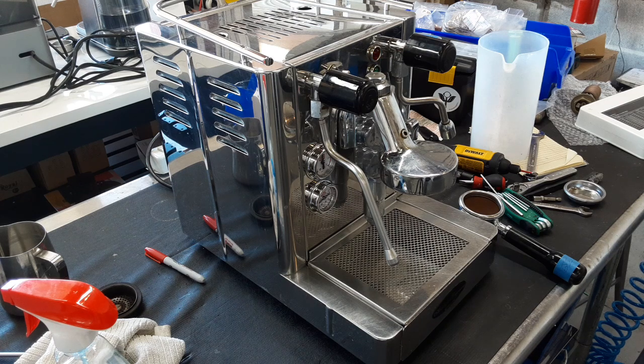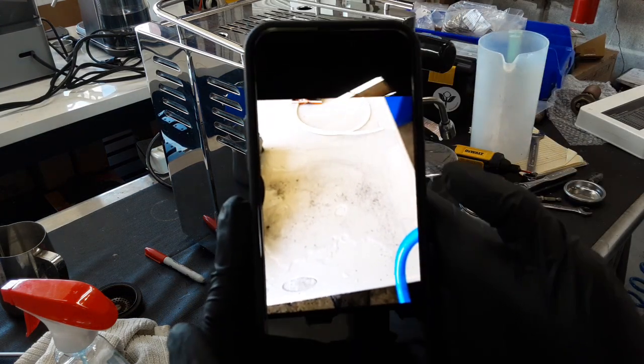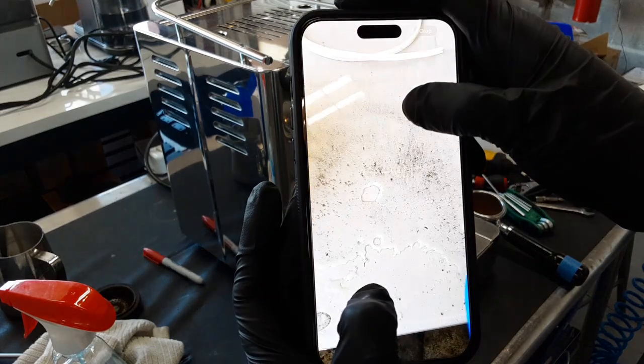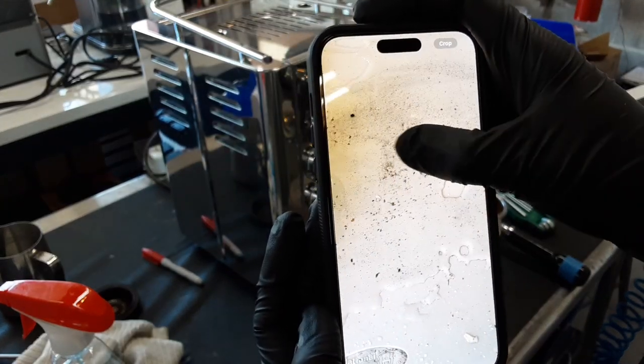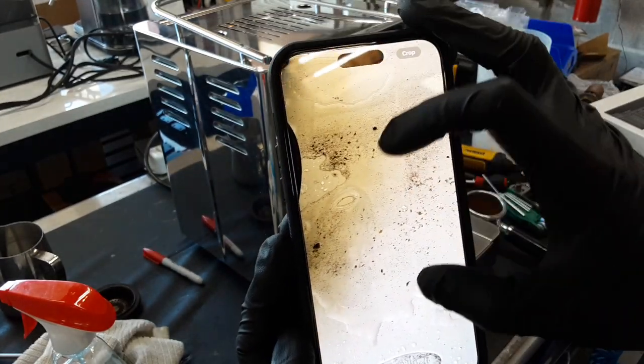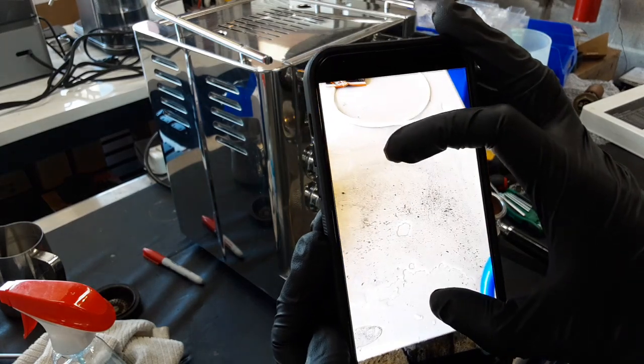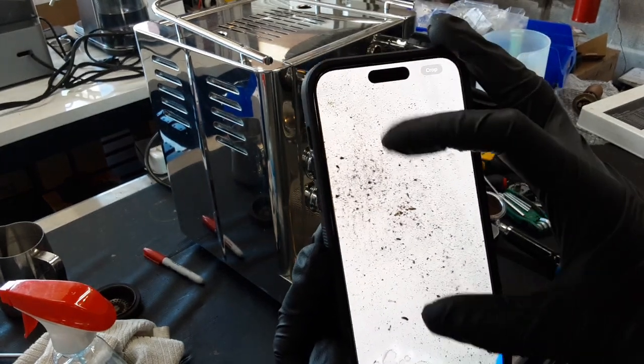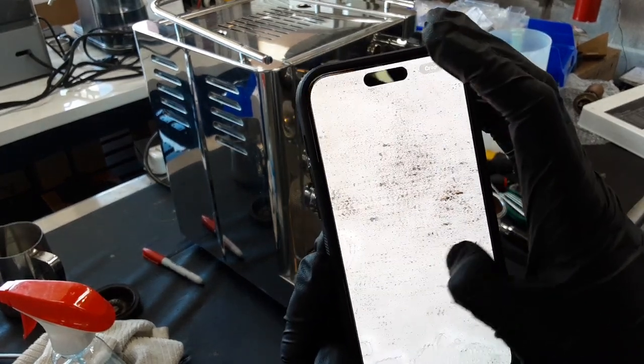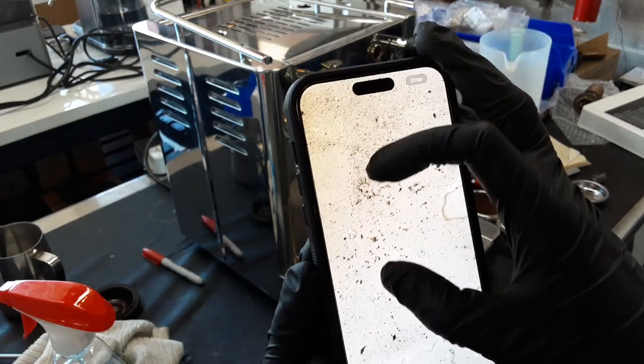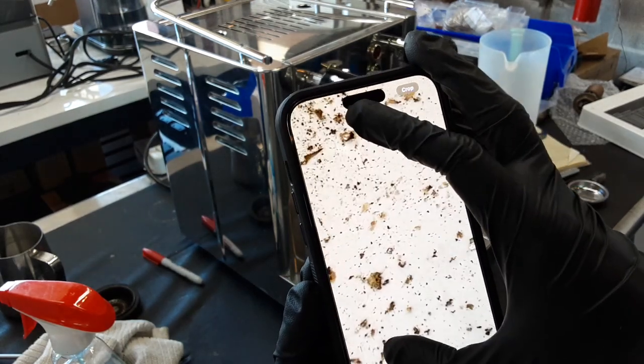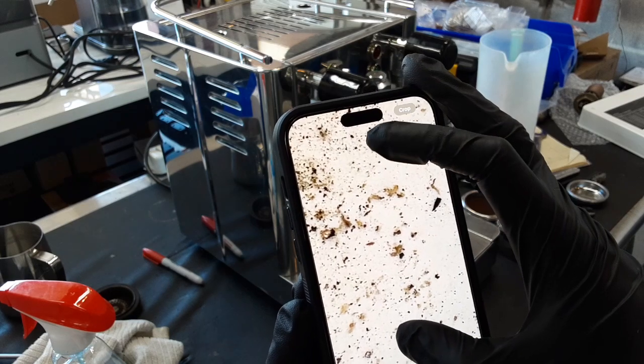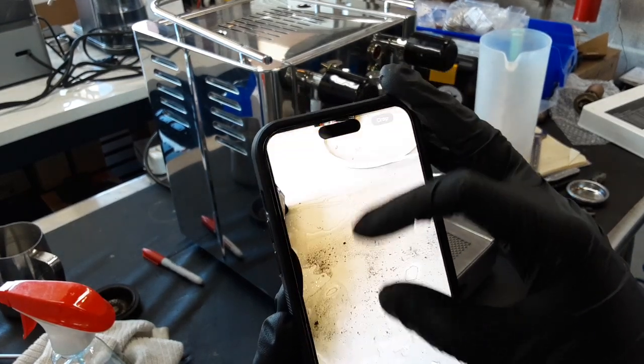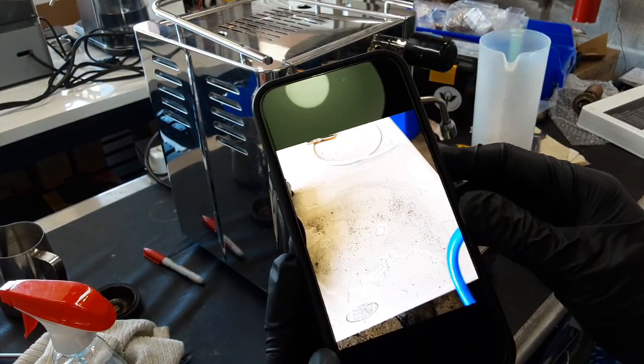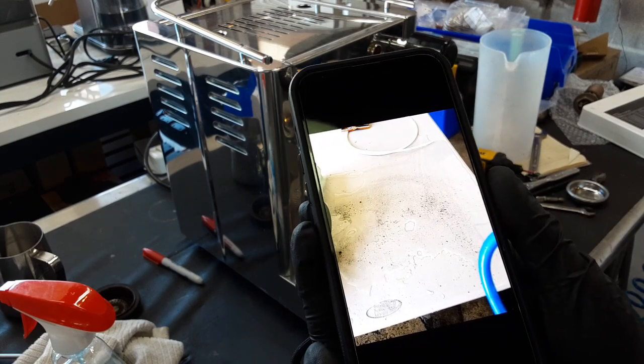Once we did that, I have a photo here. As you can see, all of that is flakes and minerals that were built up. This is from the first flush. There were definitely more flushes; we spent a few hours on it. But all of that was clogged into the machine. As you can see, it almost looks like gravel, really big pieces too. It was really, really bad. That was all inside of your boiler, and that was what was inevitably inside of the water pump.